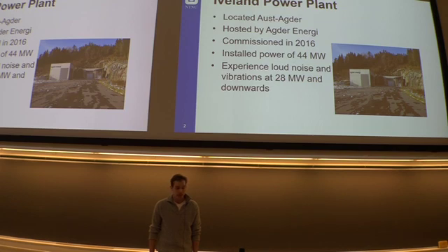The turbine experiences loud noises and vibrations when it's running at part load from 28 megawatts and downwards. And Agder Energi has asked for help to find out what's causing these vibrations and noise.